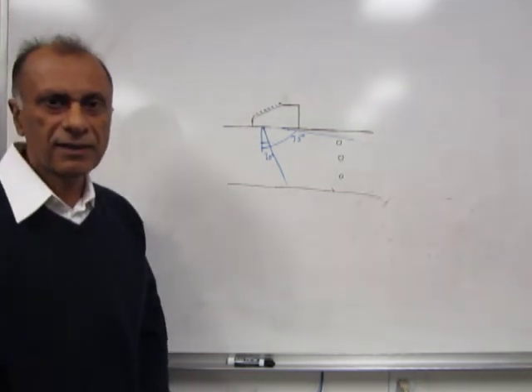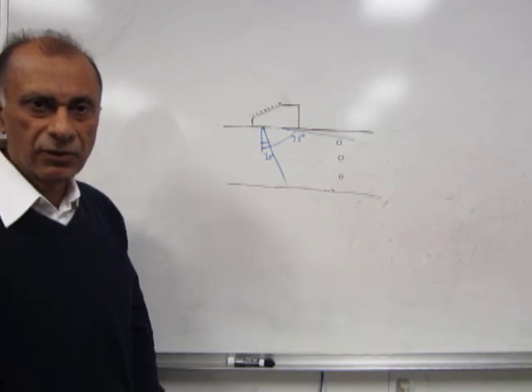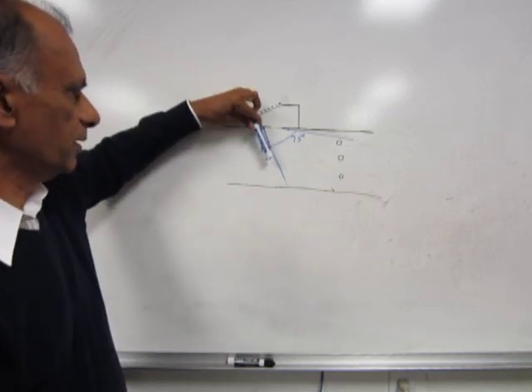Here, because we are inspecting the welds we will have to go underneath the cap of the weld, so we sweep the beam from like 30 degrees to 75 degrees.